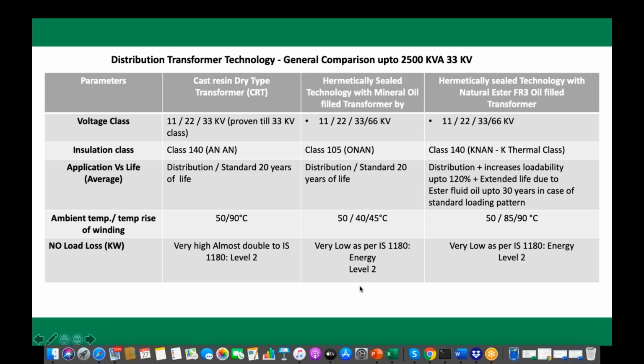The main parameter where we really make transformers inefficient is when you do a dry type transformer, because I understand that product a little better. I spent almost 20 years in it, out of my 30 years of career. When you talk about no load losses, it's close to impossible to match the no load losses of a liquid filled transformer because of its size. Normally, no load losses in a dry type transformer are almost double those of a liquid filled transformer.